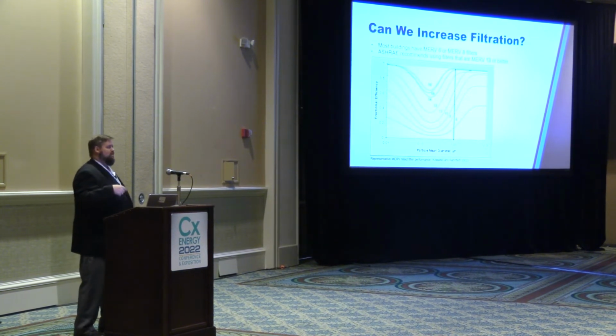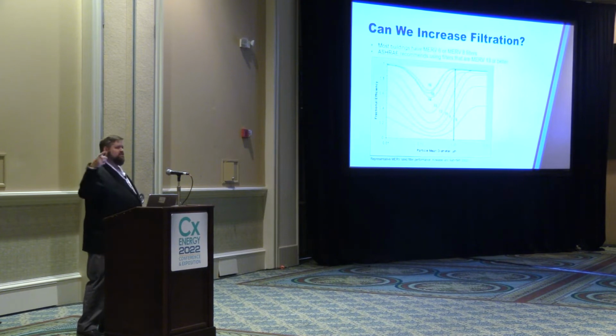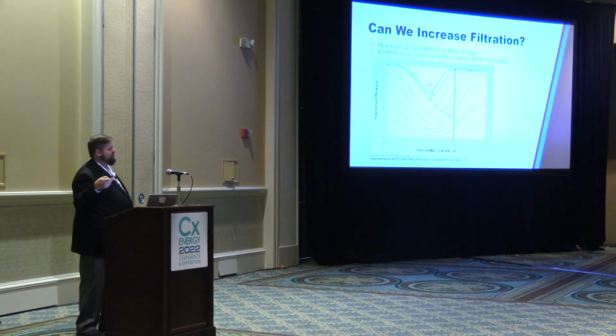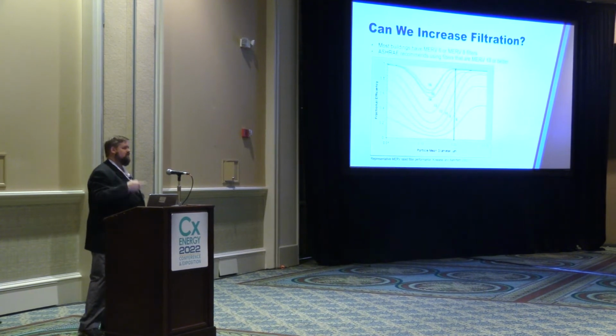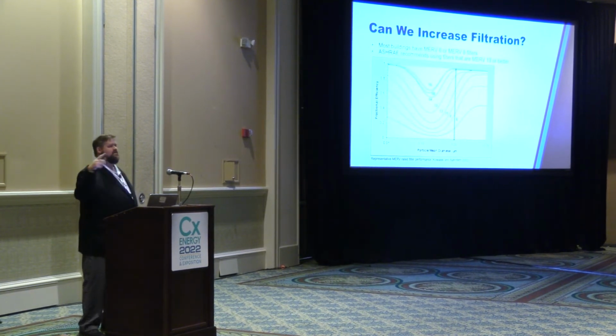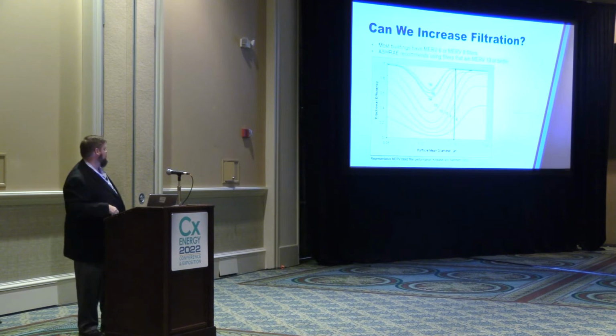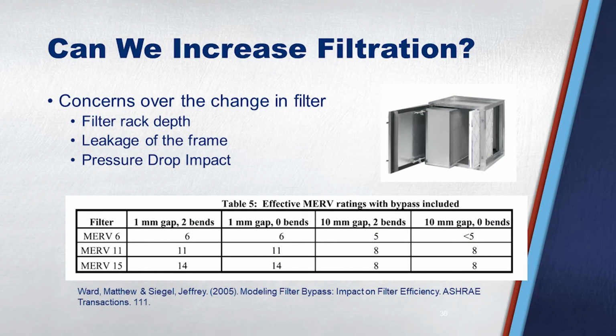But if you're evaluating this, find out what filter you do have, because chances are it's not on the existing drawings that tells you what was the dirty filter allowance. But find out the filter that was installed, and then look for a filter that's not that bad in terms of a higher rate or higher pressure drop. A key thing on filters, though, is how well are they installed?